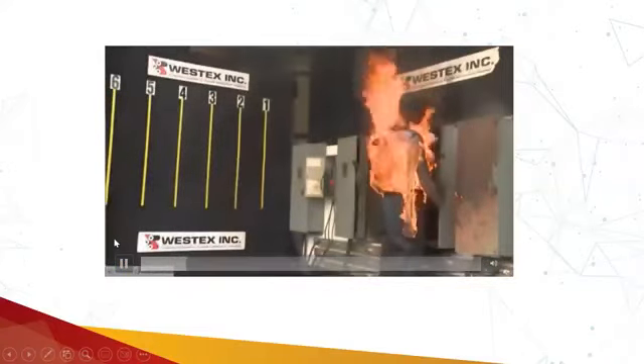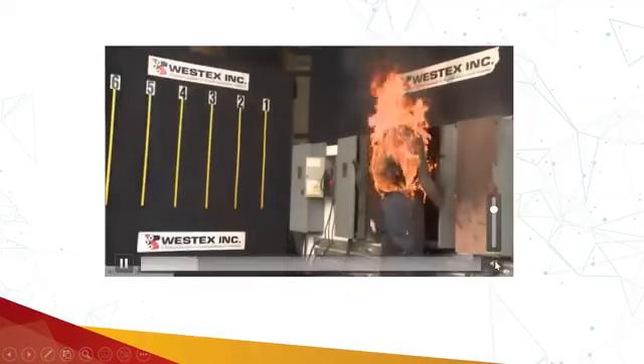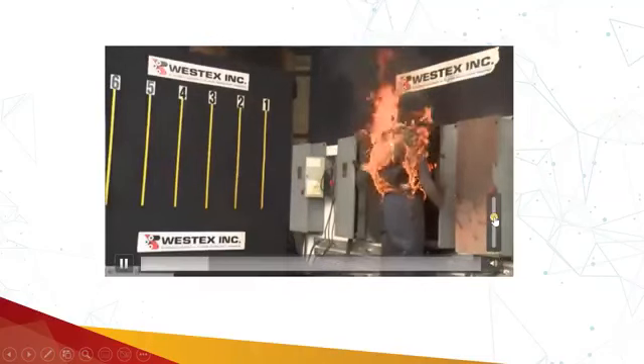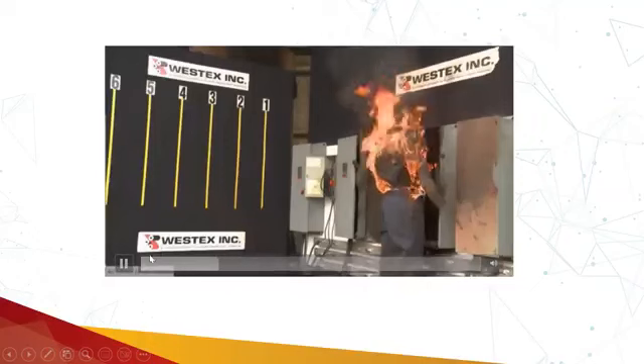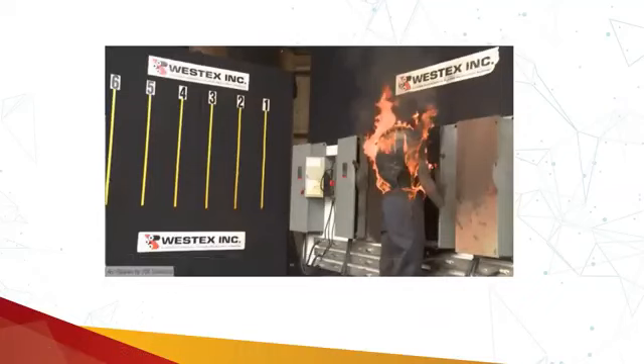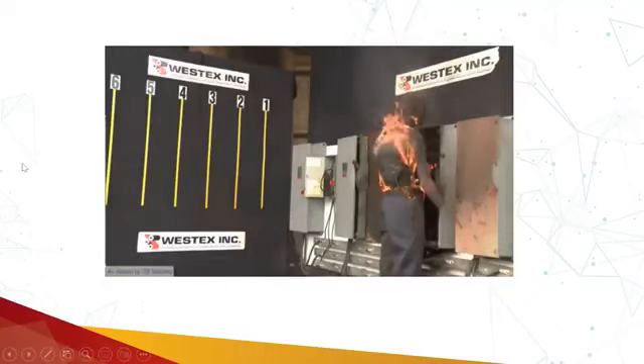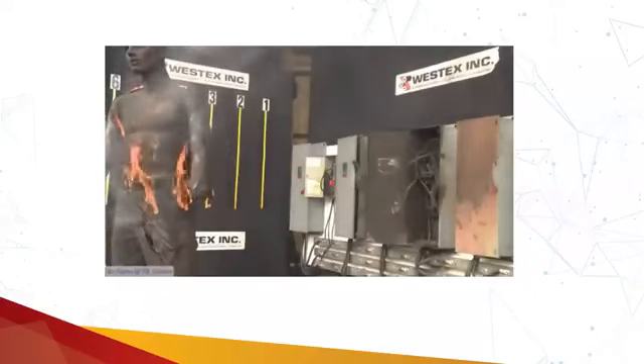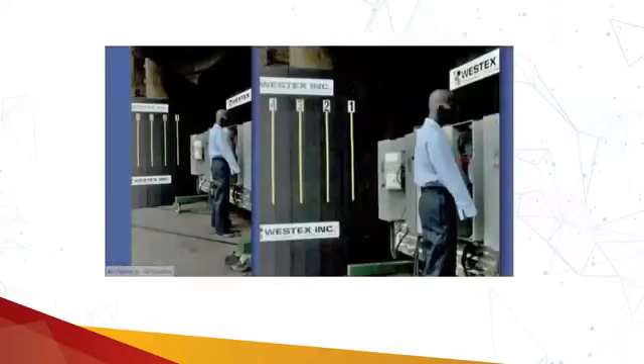And notice that the back of the garment is on fire immediately, even though the arc never hit him in the back. Stop, drop, and roll is not going to put this out. This fire is too aggressive. So the arc flash event is over because it has been interrupted by the operation of the fault current, but this thermal event is still on. The pants are on fire as well. It's hard to see right now, but when our firefighter moves the mannequin, you can clearly see that the pants have ignited as well, and the shirt within seconds is almost completely burned off the mannequin.